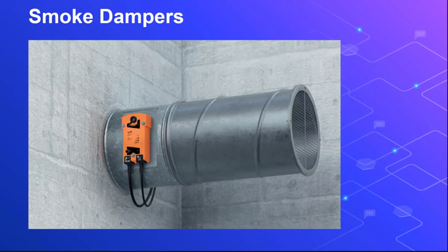The spring does not have a return mechanism. In the event of a fault, such as cable breakage, short circuit, or open circuit, the damper does not change its position. The cable must be fire resistant. It has to be fed from a continuous source, which is a backup source.